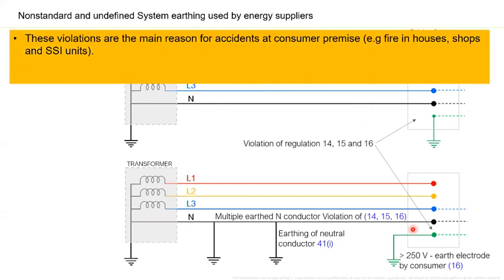In a TT network, you require a 30 milliampere RCD at the origin of installation, and you will have additional problems as well. Whereas if you look at a medium size industry where they have, let us say, 50, 60 kilowatt of connected load on a low voltage LT supply, working with a 30 milliampere RCD at the origin of installation probably may not work because of the inherent leakage current of the devices. So these violations are some of the reasons for accidents at the consumer premise.